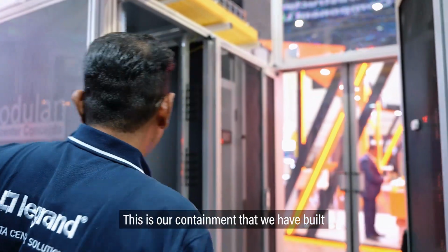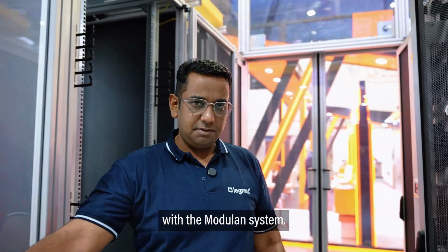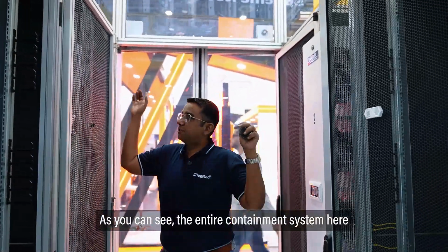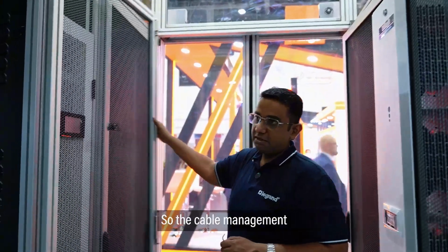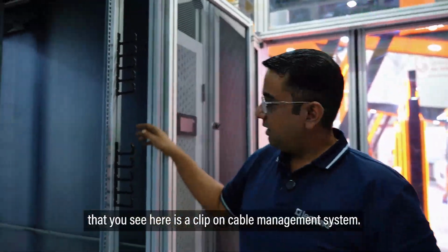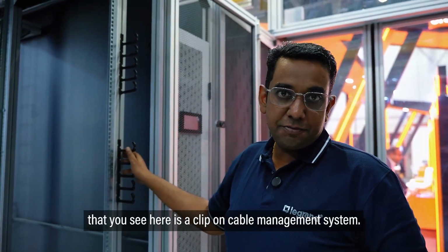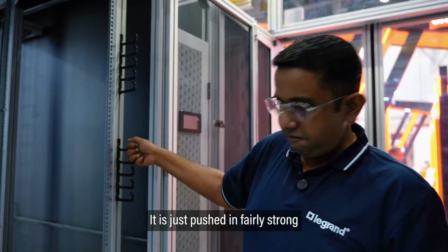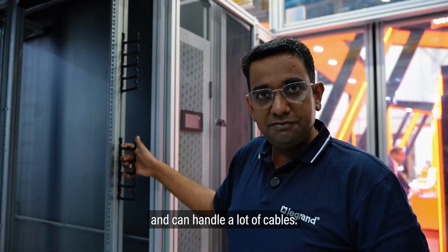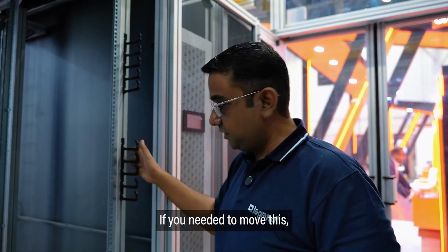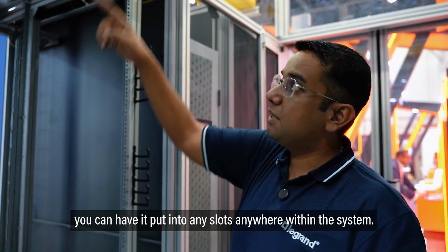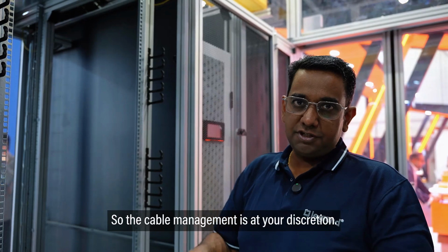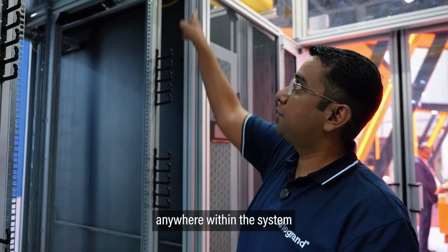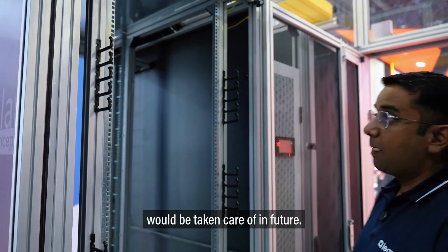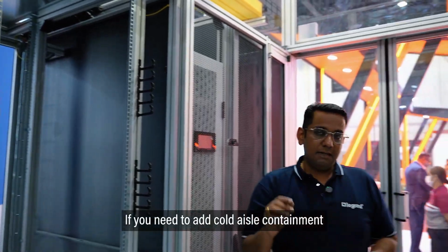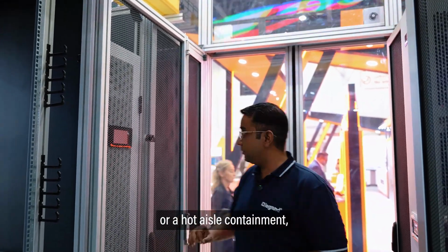This is our containment, built with the Modulan system. As you can see, the entire containment is built with the exact same profiles. The cable management you see here is a clip-on system, no tools needed, just pushed in, fairly strong, and able to handle a lot of cables. If you need to move it, it can be put into any slot anywhere within the system, so cable management is entirely at your discretion. You just push them into the slots anywhere within the system and the cable management is taken care of.